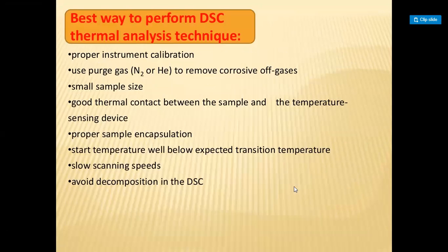The best way to perform DSC is proper instrument calibration, use of purge gas, and good thermal contact between the sample and the temperature sensing devices.